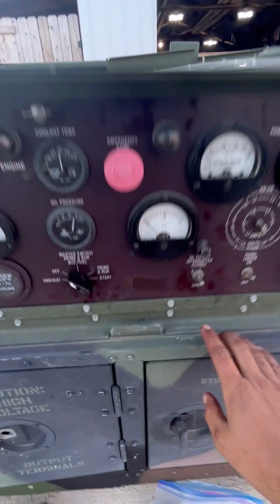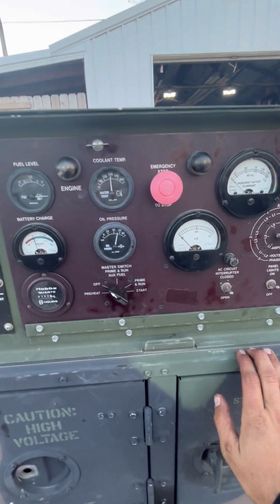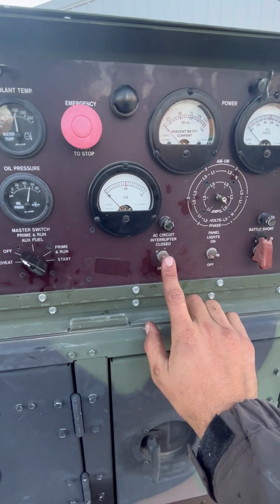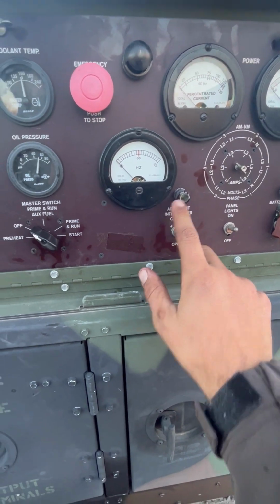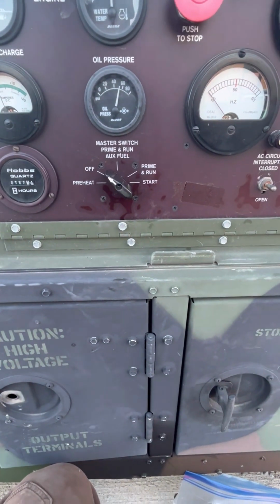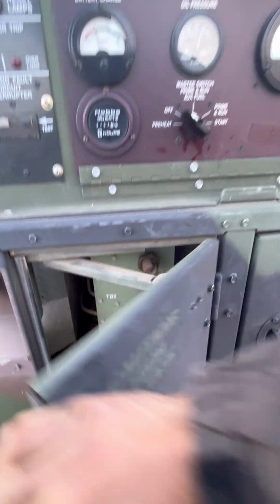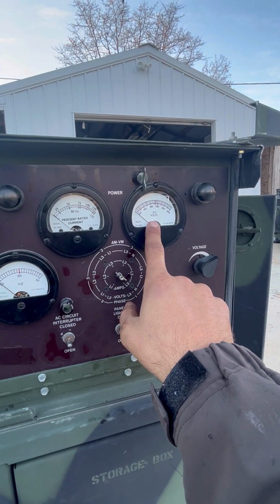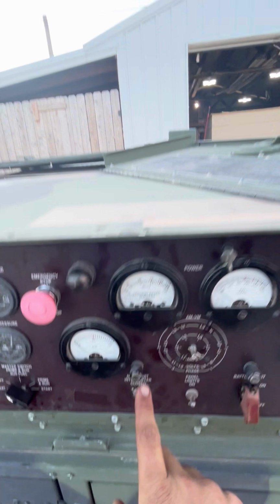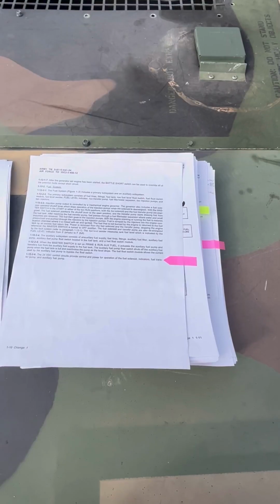Another issue that I'm having, and I'm not sure whether this is related to the CB1 breaker, is that the AC circuit interrupter is not closing. So I'm not getting any voltage out of the lugs here. I'm reading voltage here, but I'm not down here, and it's not opening or closing the circuit.